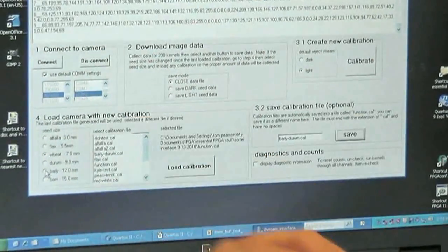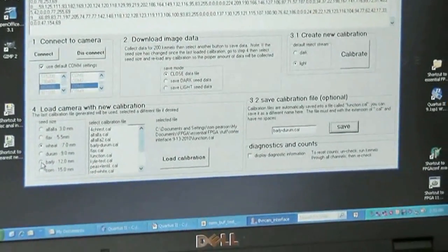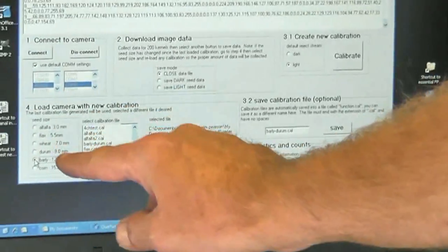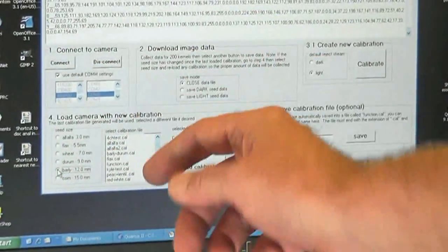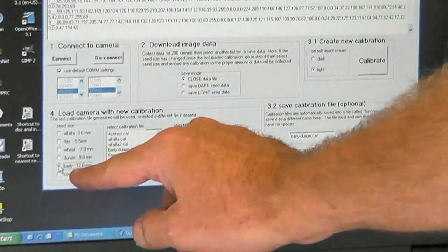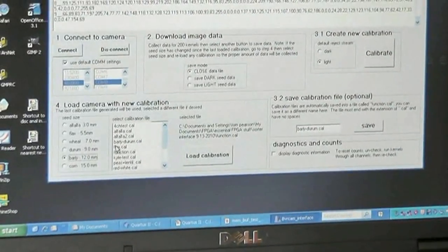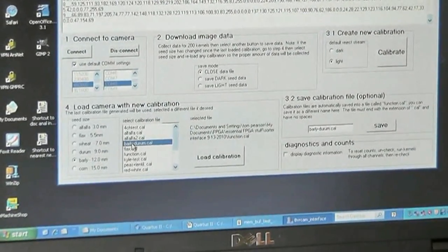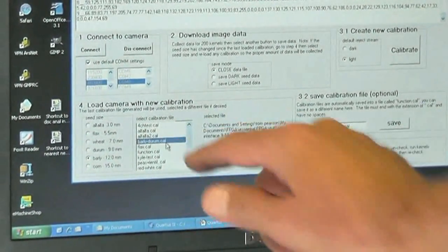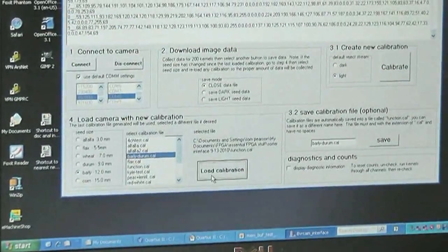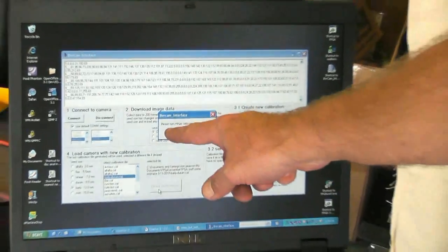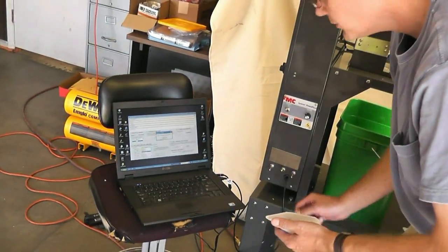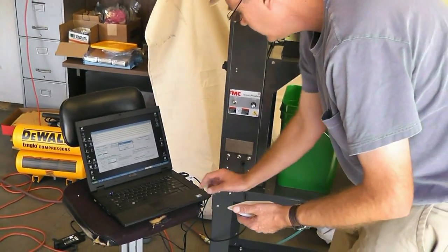So now we're going to load the calibration onto the camera. Again, we need to select the seed size. You want to select the largest seed size that you're going to be running, and that's barley here. And then we're going to select the calibration file we just did, barley-durum, and then load calibration. It says, please turn FPGA calibration switch to on. Switch that on.